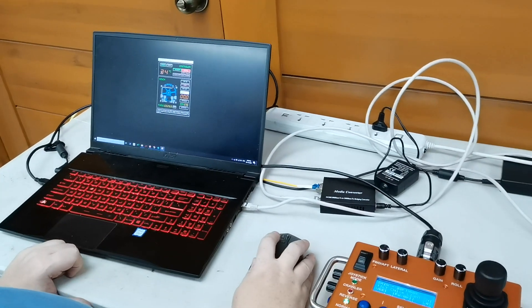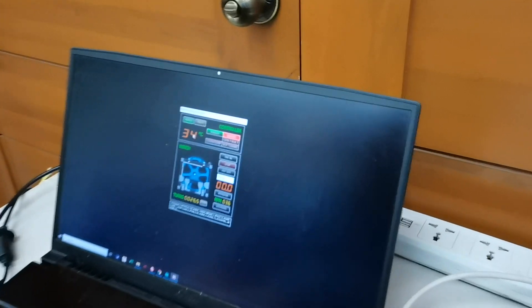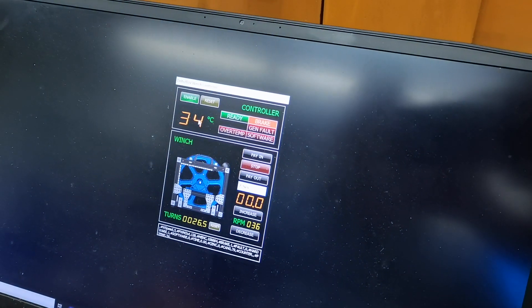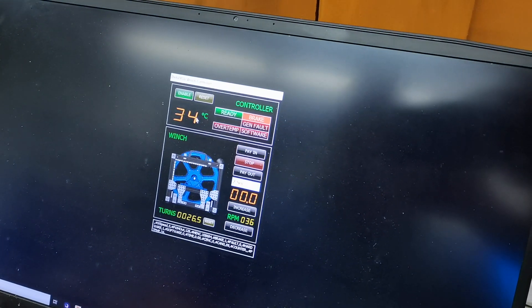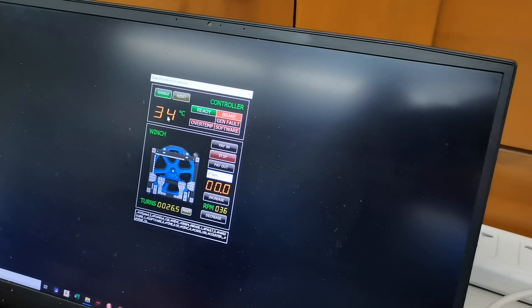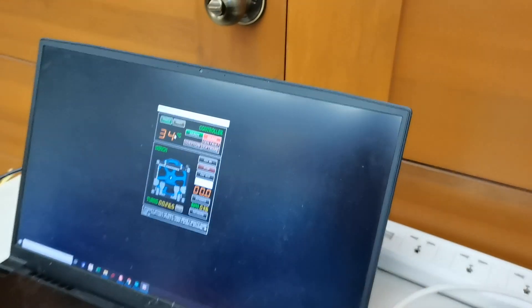This, over here, you have the temperature. This is the actual temperature that's inside the winch power controller. And as mentioned earlier, if it reaches 40, the fans will turn on. And it will turn off again when it's reached 30 degrees Celsius.